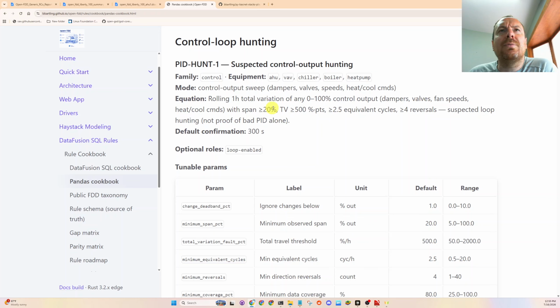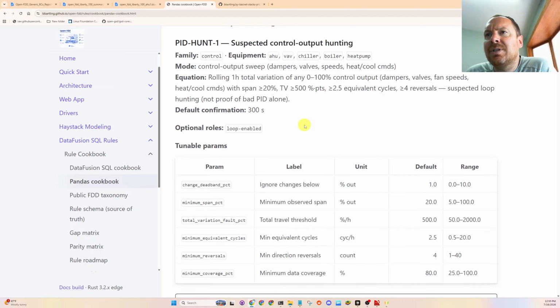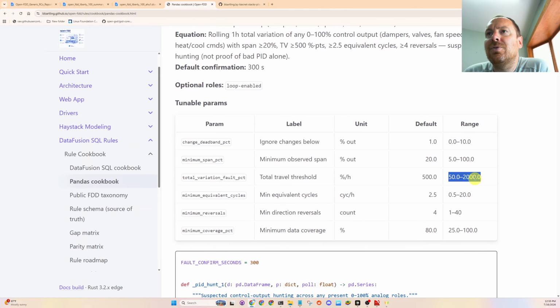So what we're doing in a simplistic way, through the course of an hour, is the control output is going like this constantly, and we're adding all of those peaks and valleys together. And then we're coming up with a total travel threshold in percent per hour, to be in the range of 50 to 2,000%.